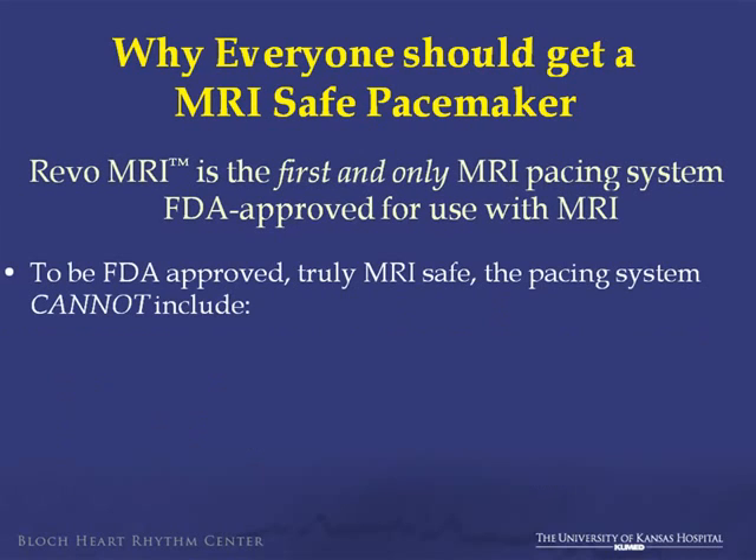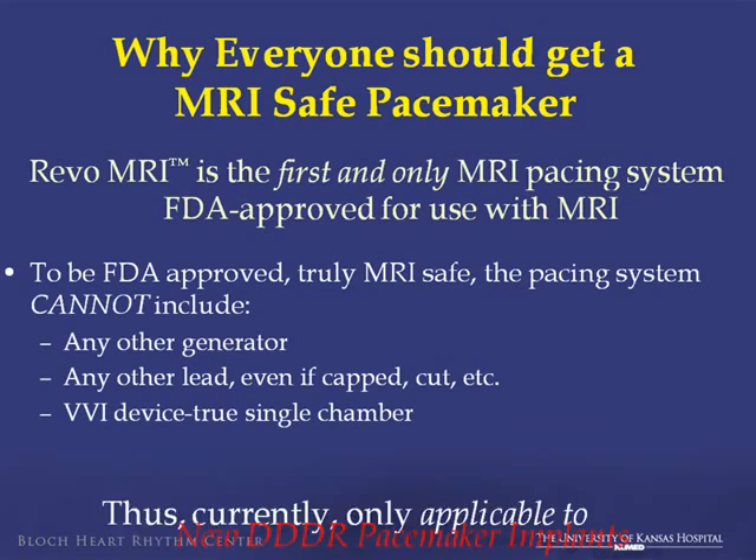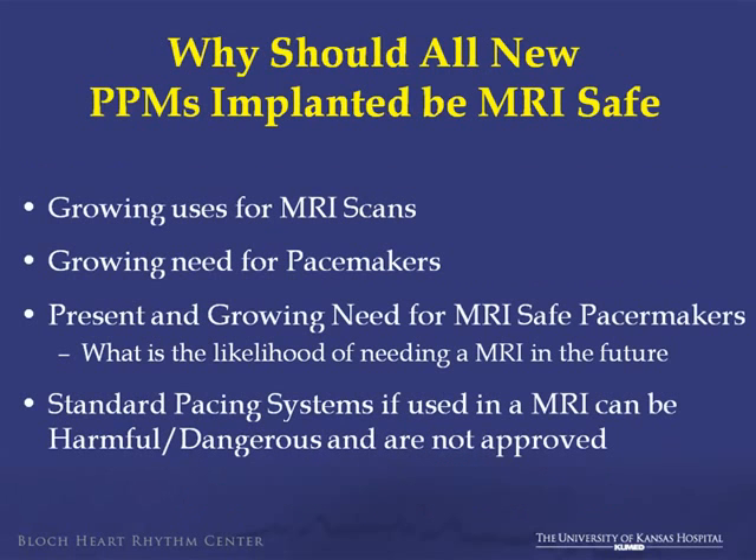To be FDA-approved and truly MRI-safe, you cannot include any other generator, any lead, even if it's capped or cut or otherwise, or a single-chamber device. So what we're really talking about is new dual-chamber pacemaker implants — why should all new pacemaker implants be MRI-safe pacemaker implants.